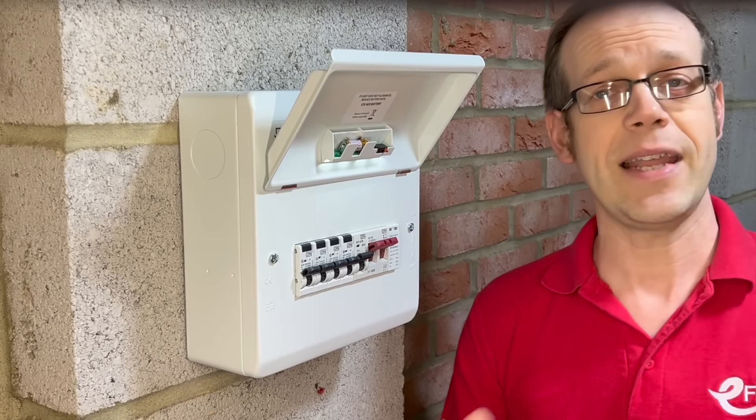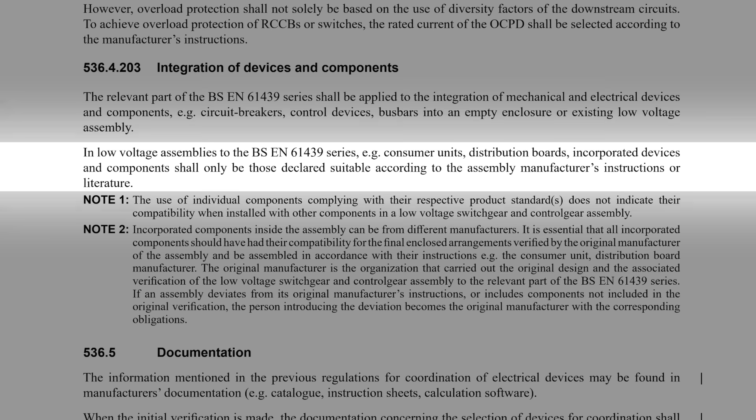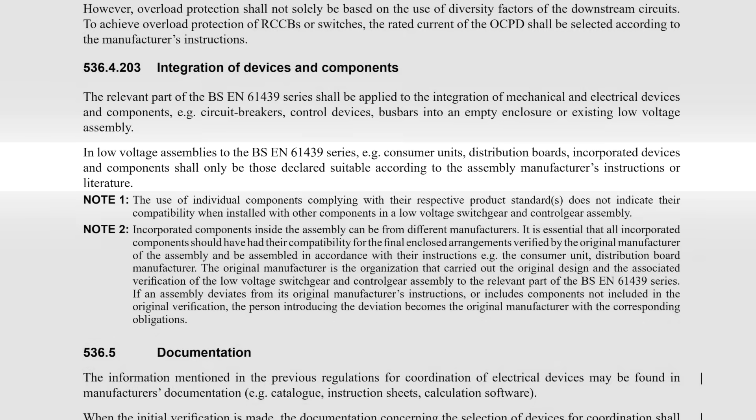This is highlighted in the next part of regulation 536.4.203: in low voltage assemblies to the BS EN 61439 series — e.g. consumer units, distribution boards, and so on — incorporated devices and components shall only be those declared suitable according to the assembly manufacturer's instructions or literature.